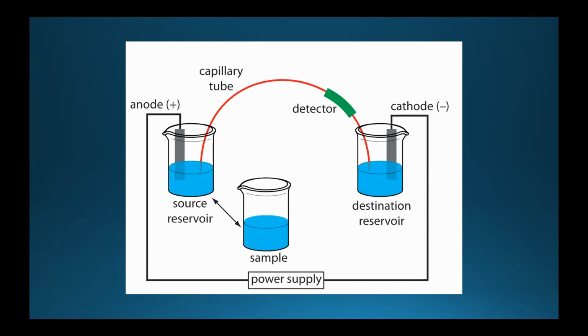There's a narrow capillary tube, in the millimeter scale, which runs through from one electrode to the other. It is first flushed with a buffer before it's introduced to the sample, and then the sample is injected either by pressure differences or by applying a voltage. The sample is very, very small. It's 1 to 10 nanoliters, as opposed to microliters in HPLC and other techniques. So that is an advantage I'll get into later, the small sample size.